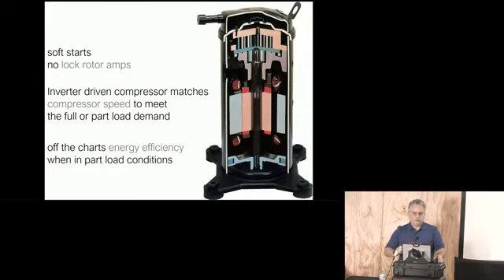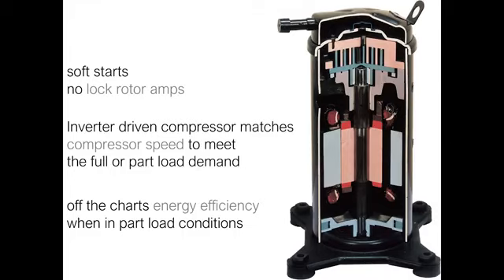Now, tell me, what job have you installed with that condition? Anybody? Yeah, neither have I. I haven't seen it. I haven't done it. So when you get that SEER rating, it is a snapshot in time. So what happens when the compressor ramps down to half the hertz, half the speed? What happens to the SEER rating? Does it go down? Does it stay the same? Does it go up? You tell me. Goes up. They don't necessarily publish that information on the residential side, but on the commercial side, there are some closer values, and we'll go over a couple of those. But that's why I wrote this off the charts.